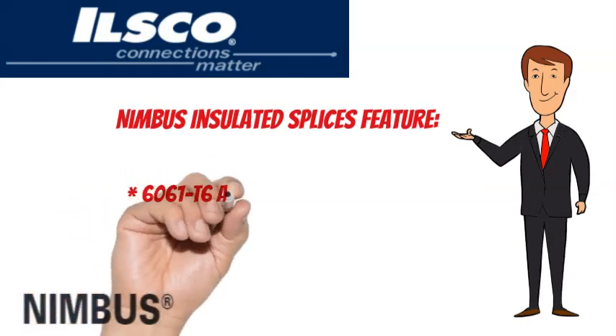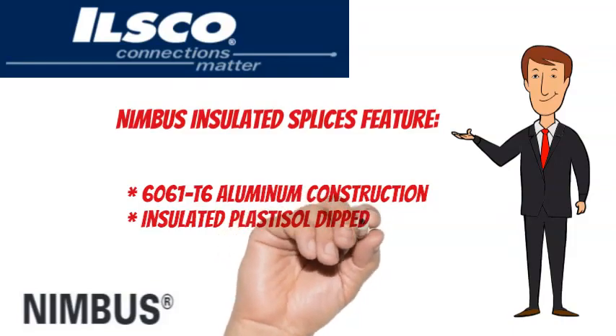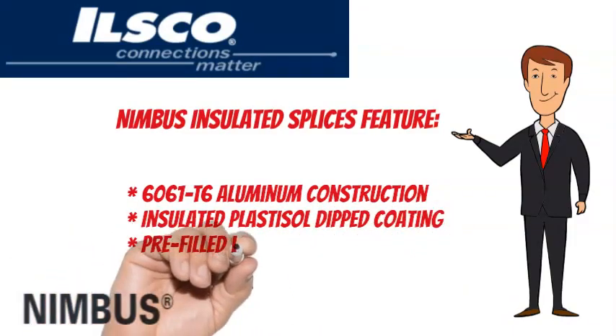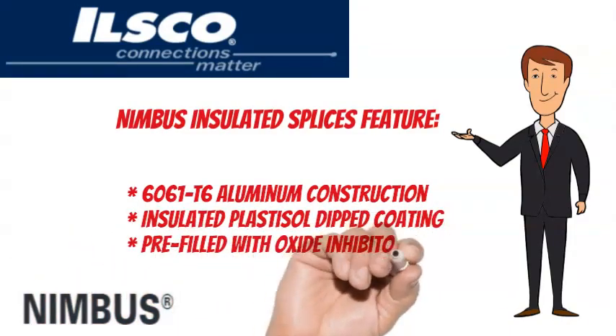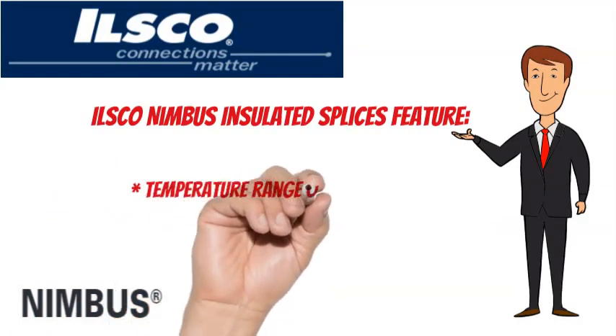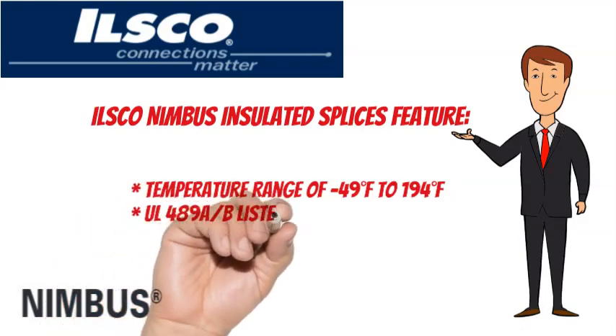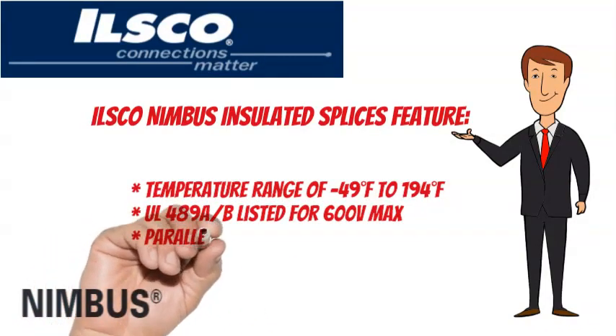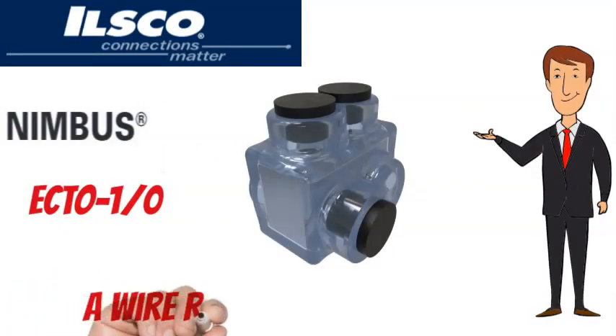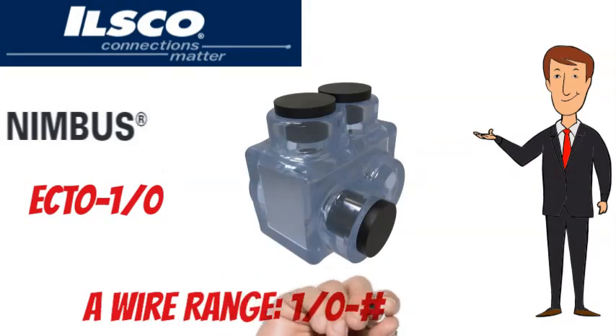6061-T6 aluminum construction with insulated plastisol-dipped coating, pre-filled with oxide inhibitor. Temperature range of minus 49 degrees Fahrenheit to 194 degrees Fahrenheit. UL 489 A and B listed for 600 volts max and are parallel rated. The ILSCO Nimbus ECTO-1/0 has a wire range of 1/0 to No. 14 AWG.